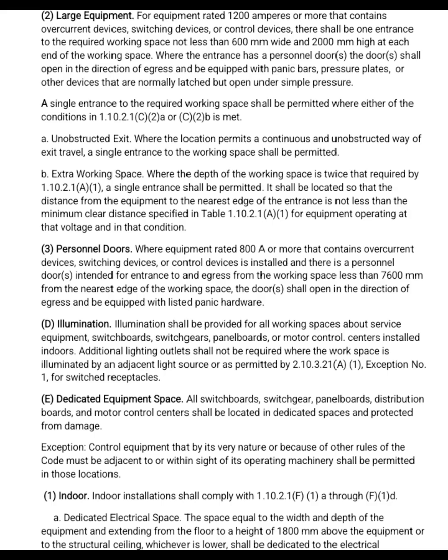D. Illumination. Illumination shall be provided for all working spaces about service equipment, switchboards, switchgears, panelboards, or motor control centers installed indoors. Additional lighting outlets shall not be required where the workspace is illuminated by an adjacent light source or as permitted by 2.10.3.21 A1 exception number 1 for switched receptacles. E. Dedicated equipment space. All switchboards, switchgears, panelboards, distribution boards, and motor control centers shall be located in dedicated spaces and protected from damage.